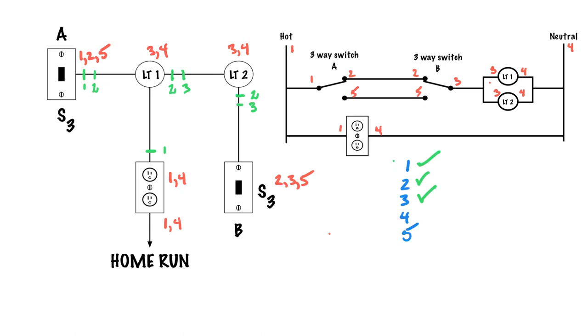Four: I have a four down at the receptacle and a four at light 1 and light 2. I don't have a four at switch A or switch B. So I take the four from the receptacle through to light 1 and light 2 — that's my neutral going all the way through. Check mark — four is done.